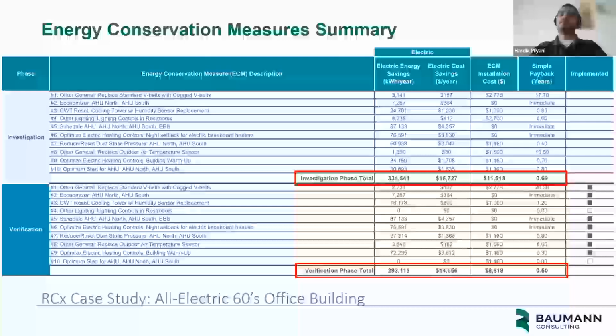So this is the final verification. We started this project with a 10% target for the building. During the investigation phase, we were able to identify almost 16% of energy savings. By the time we completed the verification, we claimed savings of almost 293,000 kilowatt hours. That is almost 14% of the annual energy consumption. The overall implementation cost for all the measures that were implemented was $8,800, and the simple payback for the entire project was less than a year.